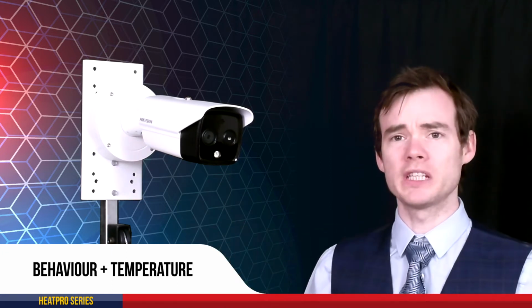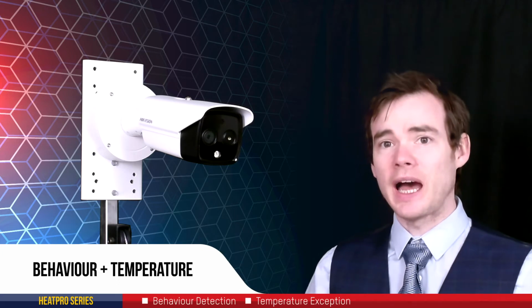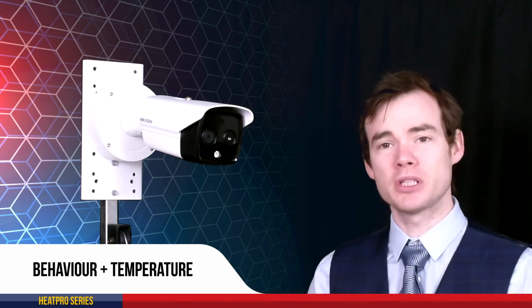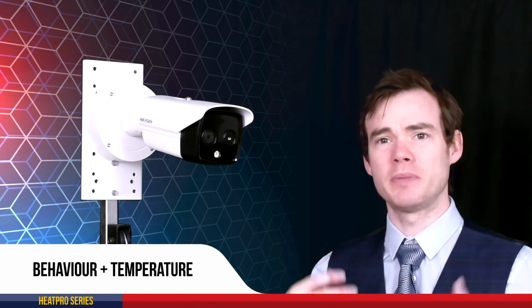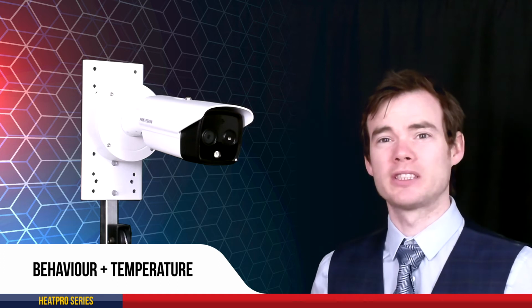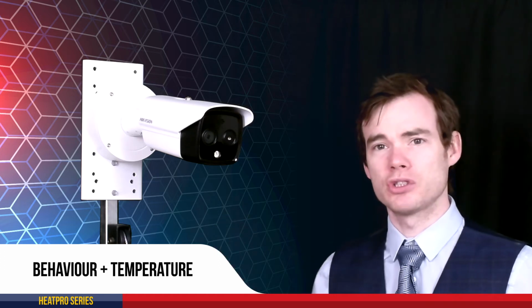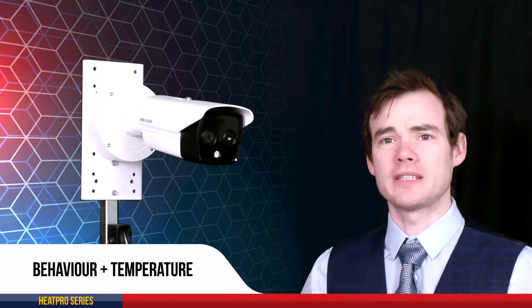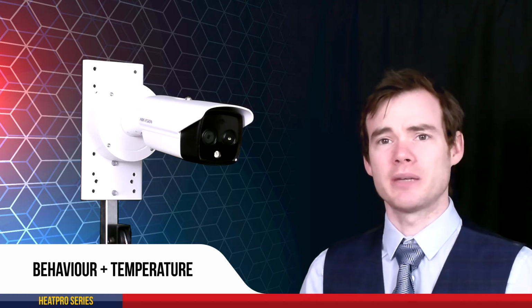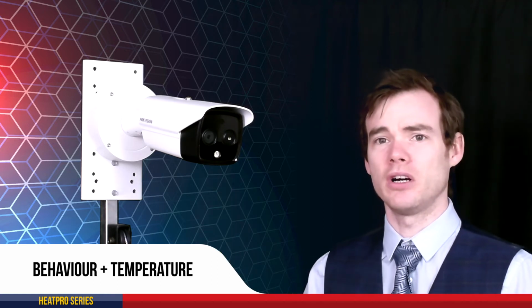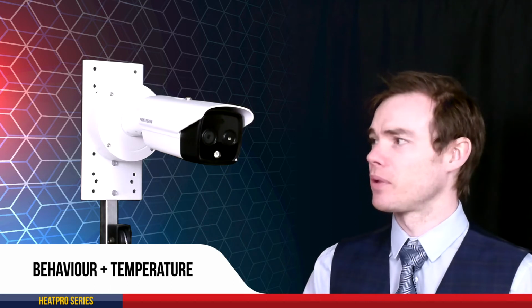Now this has an array of different features. So we can configure this to do behavior detection and temperature exception as well. Currently that's how it's set up at the minute. Alternatively, we can set it to do temperature measurement, and we can set it to do dynamic fire detection as well. Currently I've got it set up in its behavior analysis mode, as well as temperature measurement. So you can set up line crossings, intrusion detections, as well as set temperature alarms in the scene. So when a temperature exceeds that, it also sets off the audio and visual alarm on there as well.